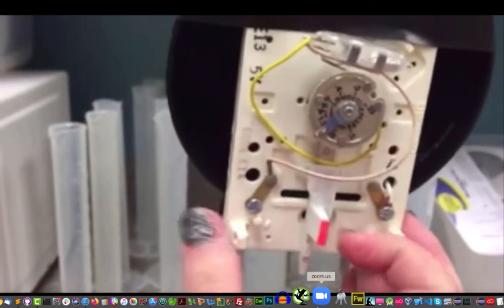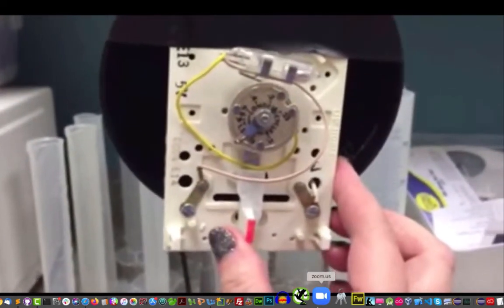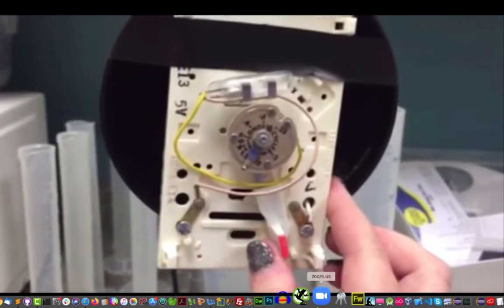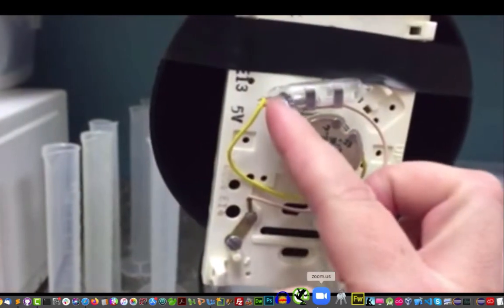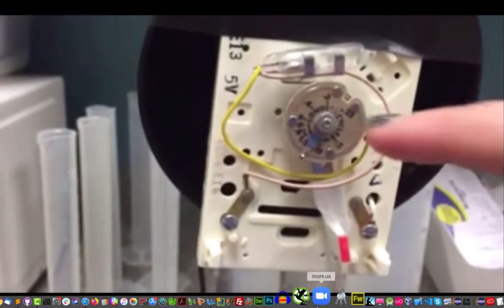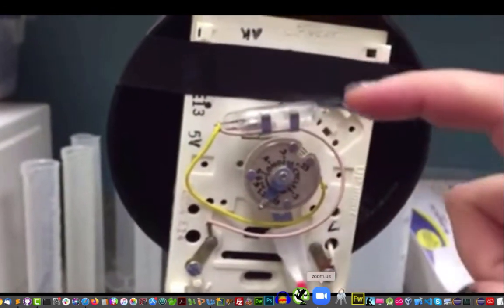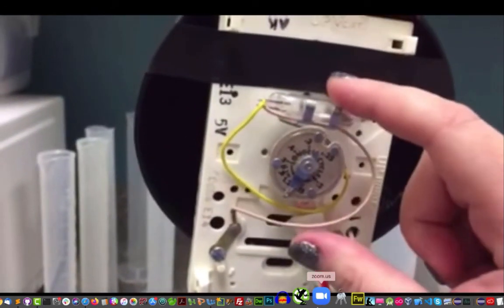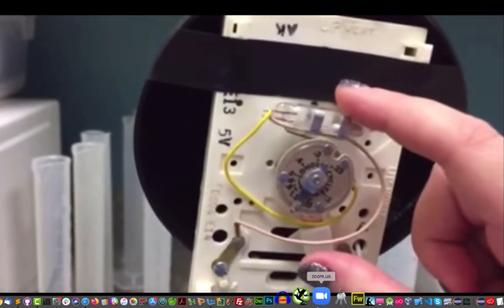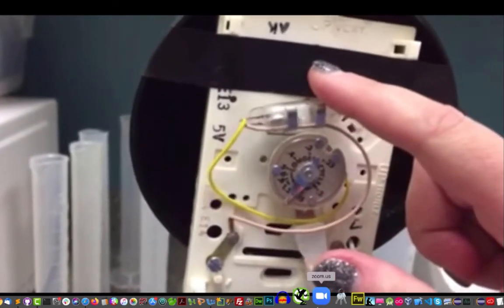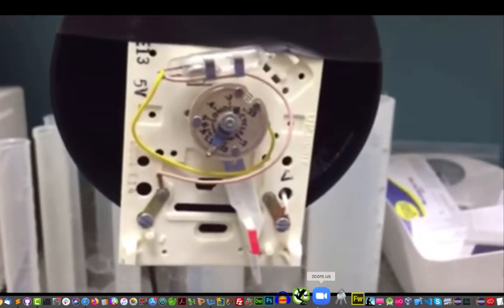So when we want to turn the heat up, that means we turn it this way, and the mercury bubble goes in to connect the circuit. The bimetallic strip will eventually heat up and it will uncoil, and it will eventually turn like this. When it cools down again, it's going to slip back and turn the furnace back on again.